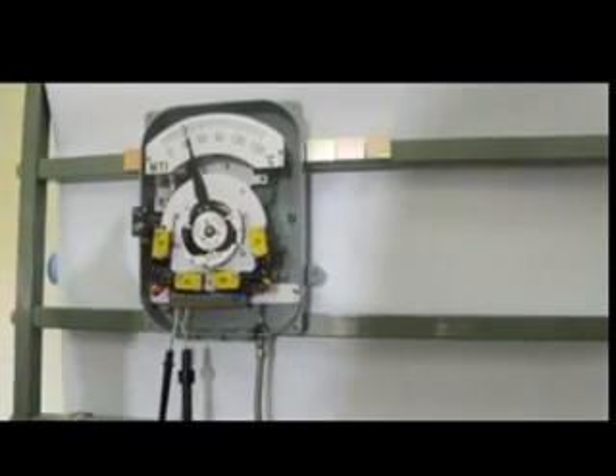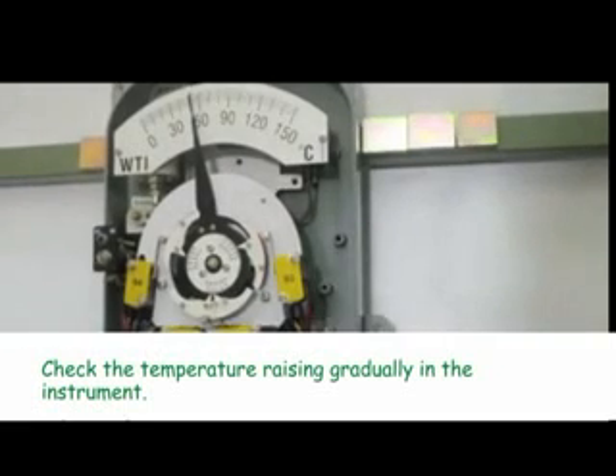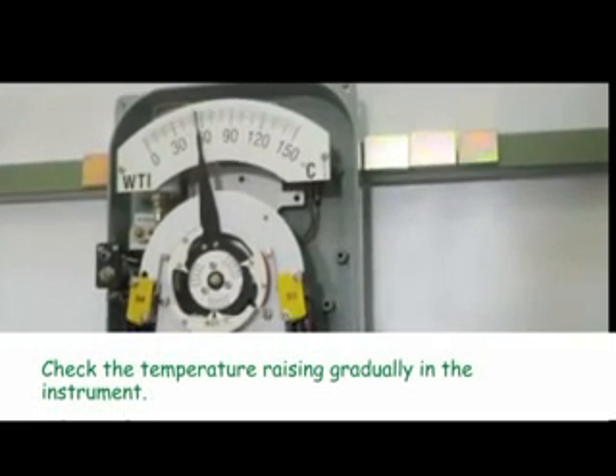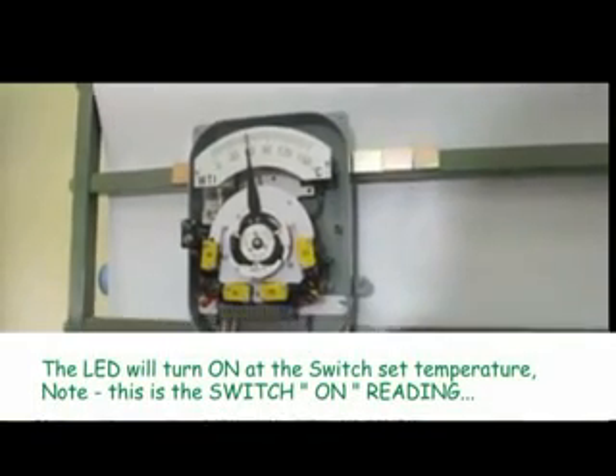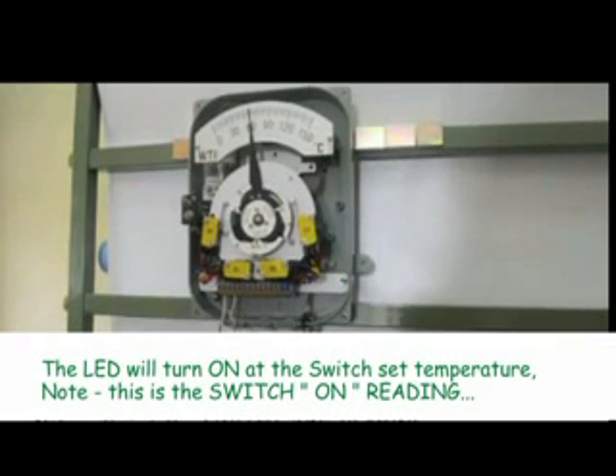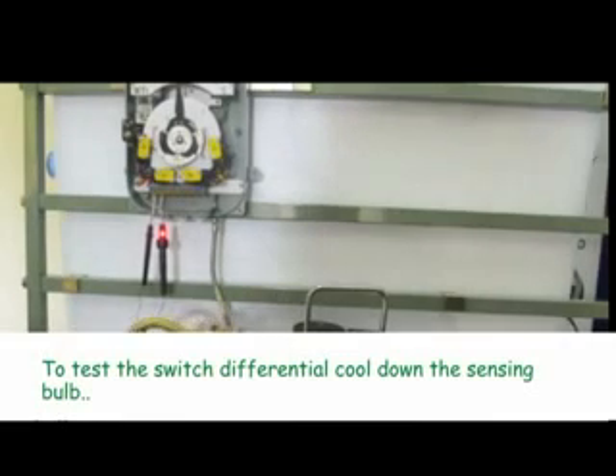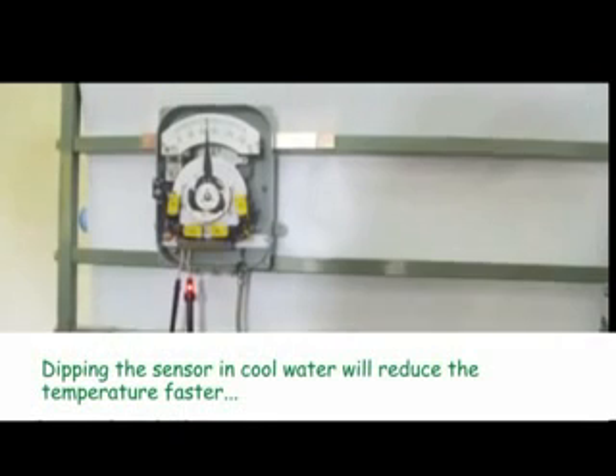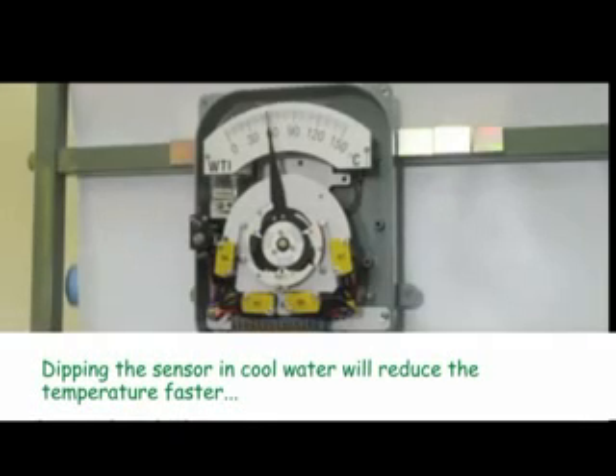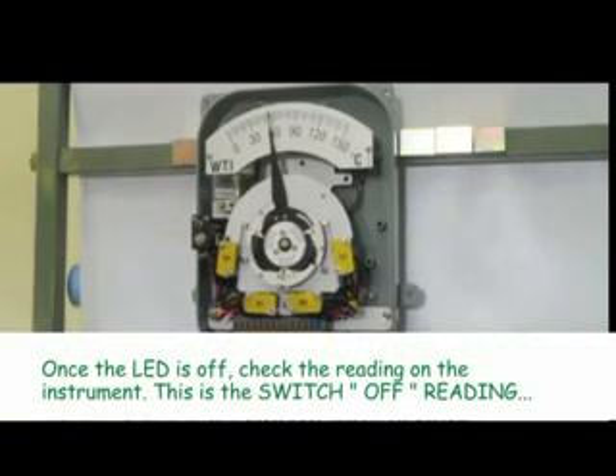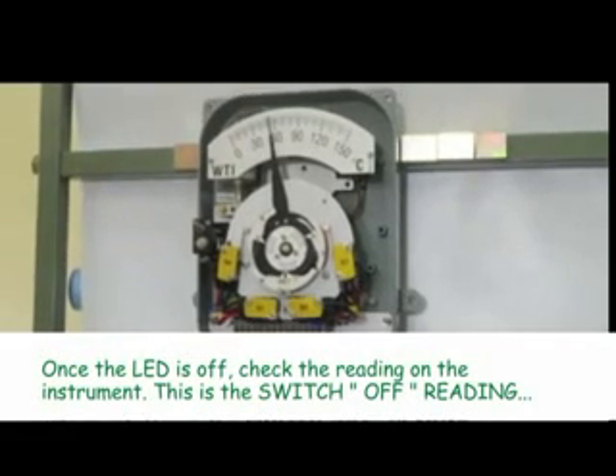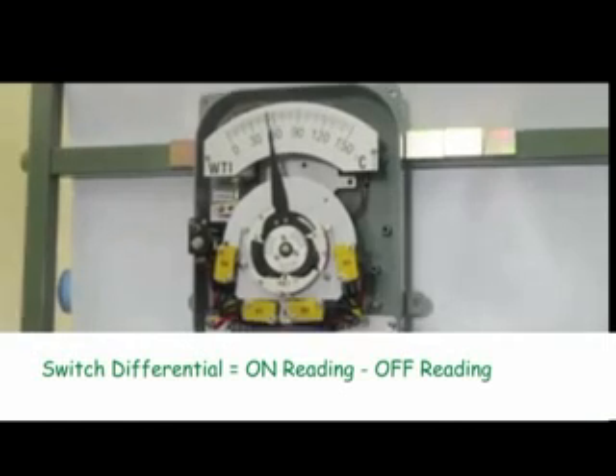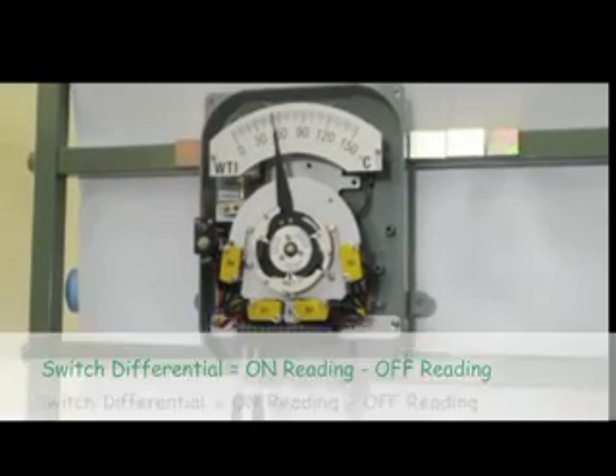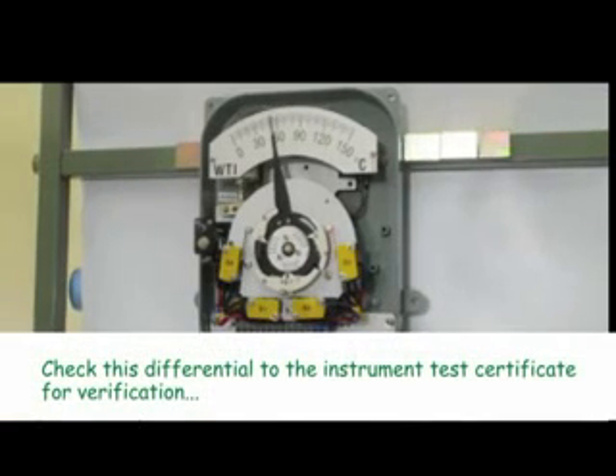Insert the sensing bulb halfway, that is, let only the tip of the bulb in. Check the temperature rising gradually in the instrument. The LED will turn on at the switch set temperature. Note this is the switch on reading. To test the switch differential, cool down the sensing bulb. Dipping the sensor in cool water will reduce the temperature faster. Once the LED is off, check the reading on the instrument. This is the switch off reading. Switch differential is the on reading minus the off reading. Check this differential against the instrument test certificate for verification.